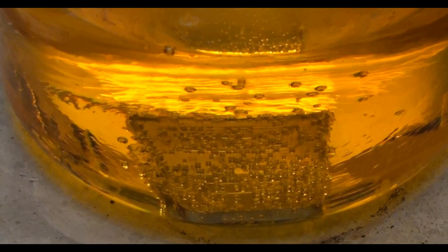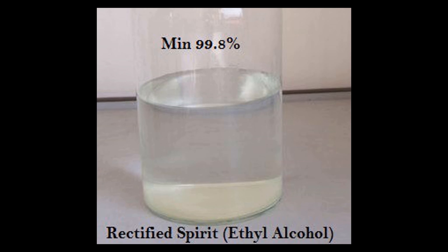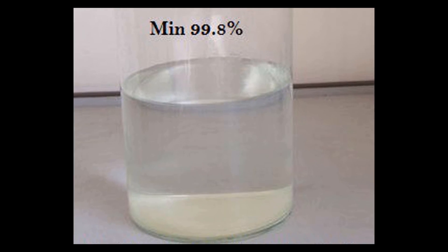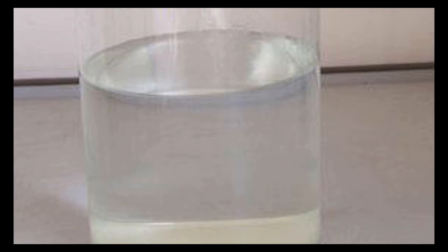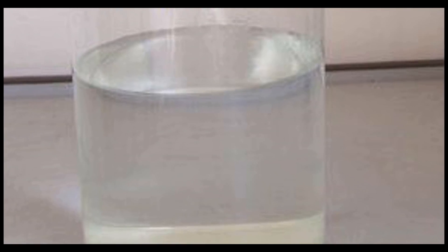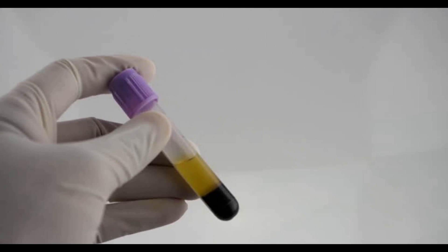Before the test, we have to extract the dissolved acid in the oil. We do this by adding exactly 1 milliliter of rectified spirit — ethyl alcohol — to the test sample. This is because the acid produced in the mineral oil is highly soluble in alcohol. After shaking the test sample well, proceed to the next step.